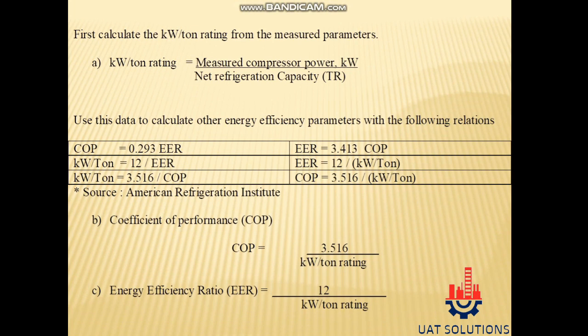Use this data to calculate other energy efficiency parameters with the following relations: COP equals 0.293 × EER; kW per ton equals 12 ÷ EER; kW per ton equals 3.516 ÷ COP; EER equals 3.413 × COP; EER equals 12 ÷ (kW per ton); COP equals 3.516 ÷ (kW per ton). Therefore: COP equals 3.516 divided by kW per ton rating; EER equals 12 divided by kW per ton rating.